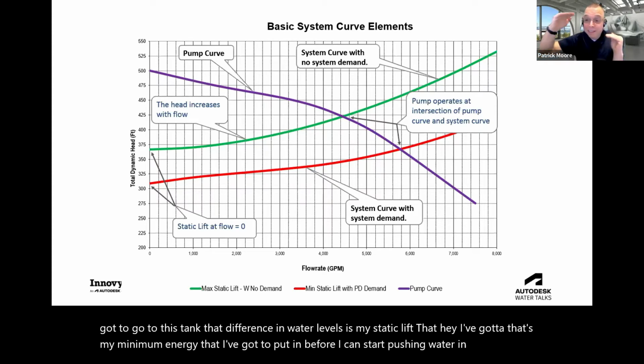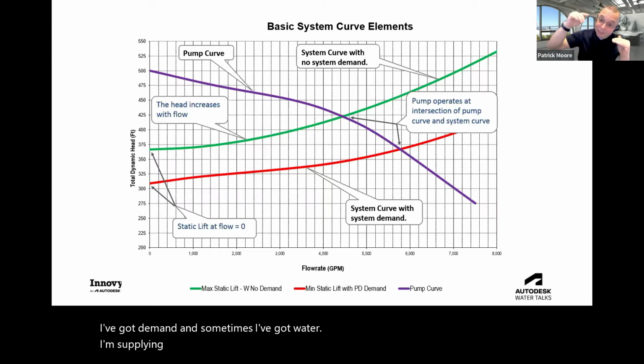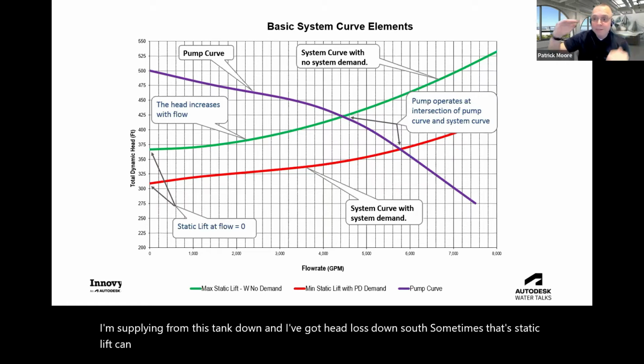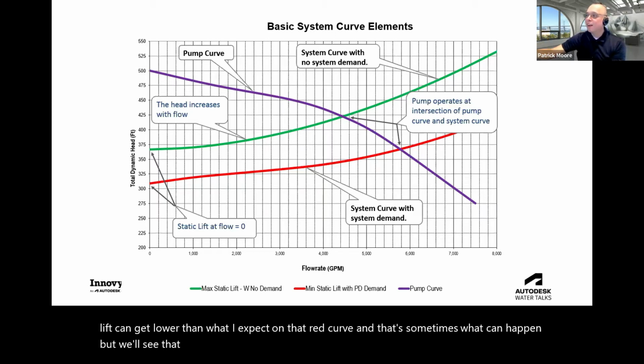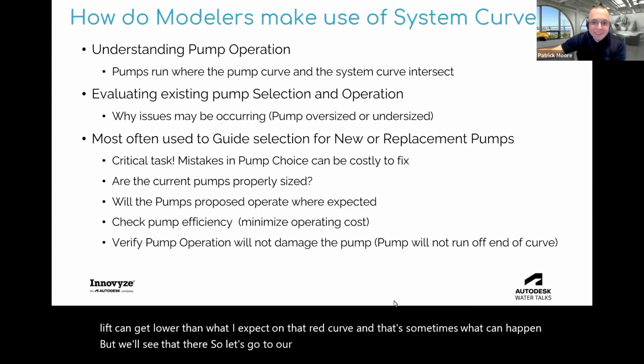If I've got demand, and sometimes I'm supplying from this tank down and I've got head loss, sometimes that static lift can get lower than what I expect on that red curve. That's sometimes what can happen, but we'll see that there. So let's go to our next slide here.